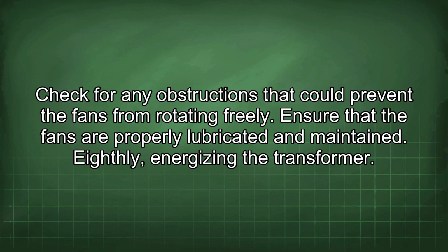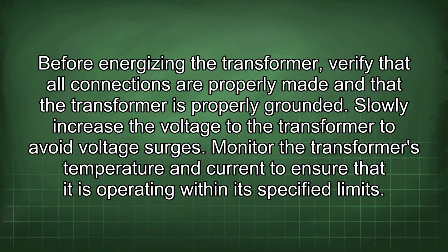Check for any obstructions that could prevent the fans from rotating freely. Ensure that the fans are properly lubricated and maintained. Eighthly, energizing the transformer. Before energizing the transformer, verify that all connections are properly made and that the transformer is properly grounded. Slowly increase the voltage to the transformer to avoid voltage surges.